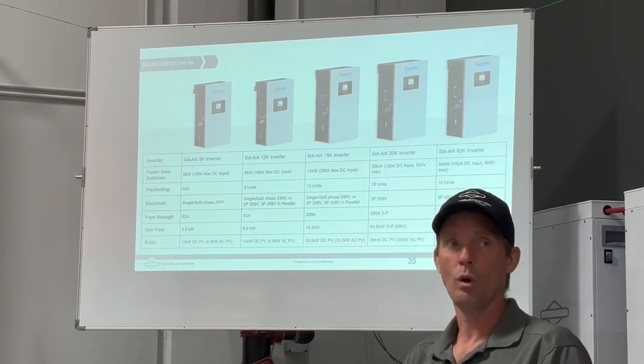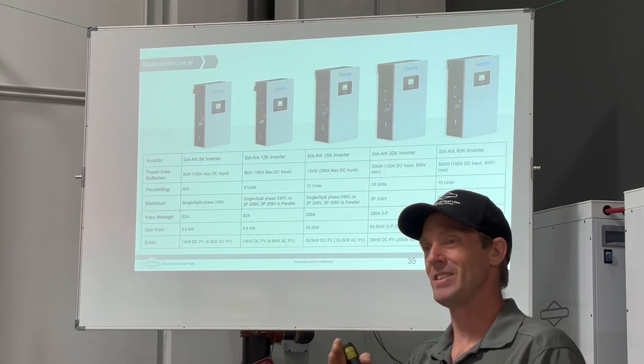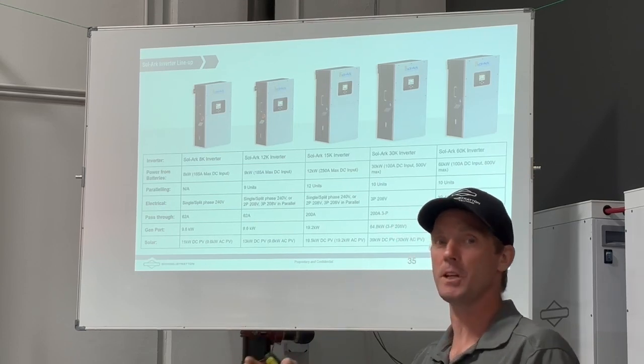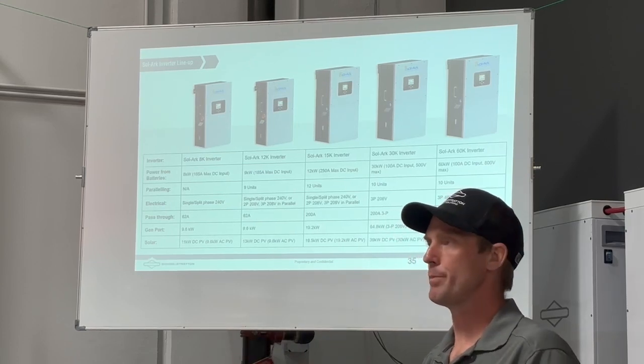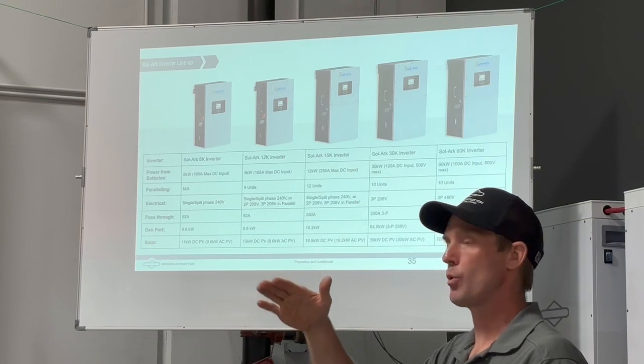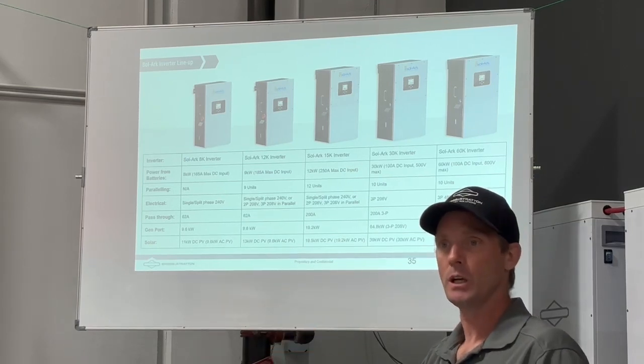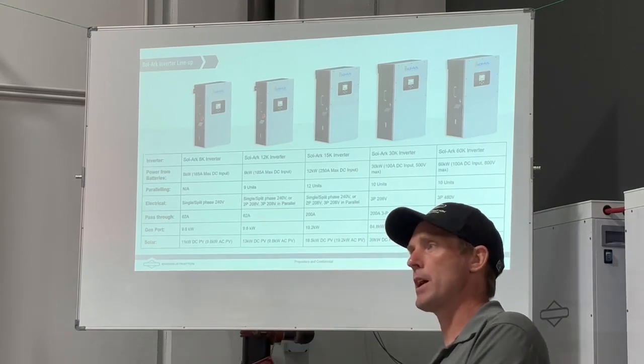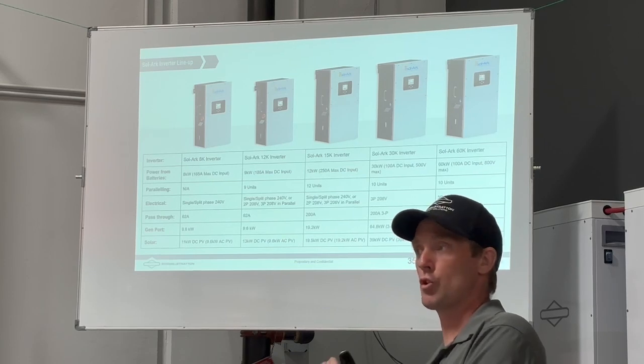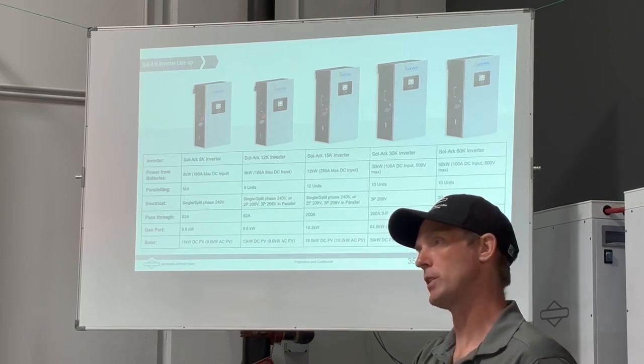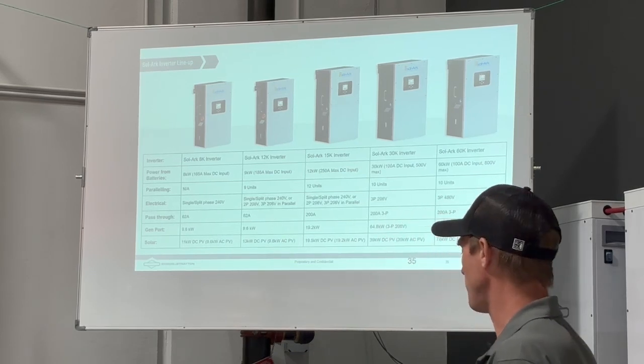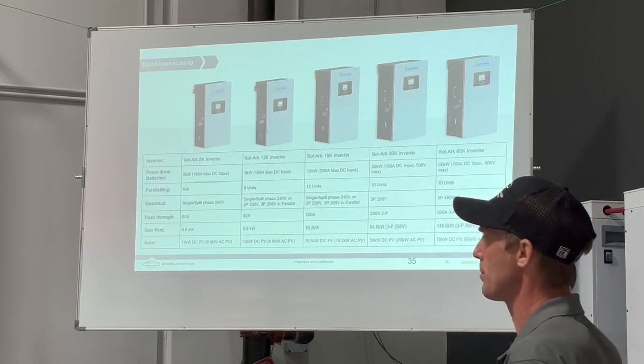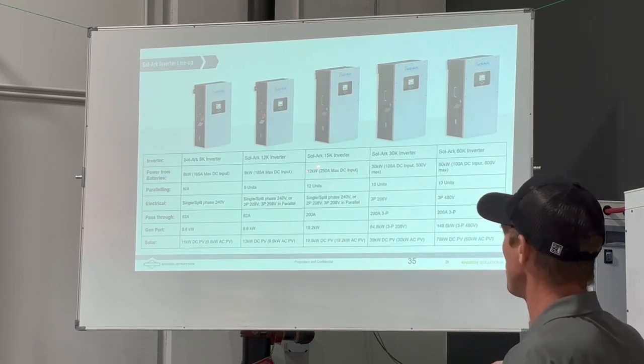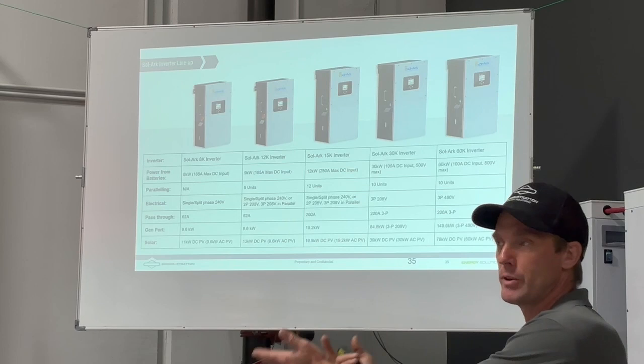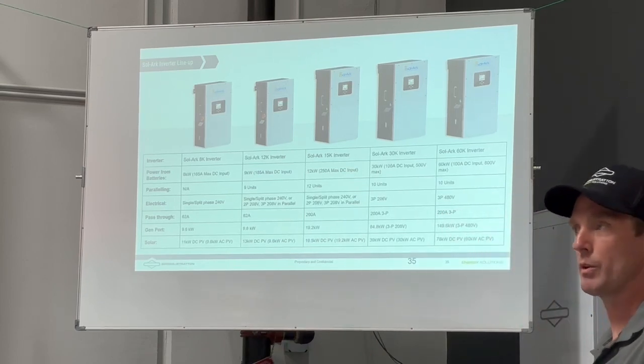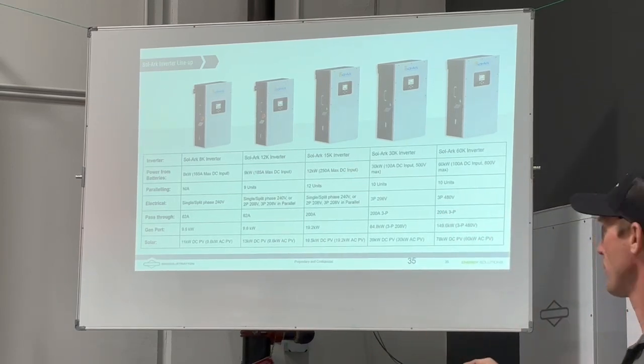I'll give you an example. The home grid battery, instead of having 16 cells in series, has 15 cells in series. So the home grid battery actually operates at about 3.2 volts lower than our battery, which means you need more current out of that battery for the same amount of power. Power is current times voltage. So if I reduce the voltage, I have to get more current. So the limitation on the 15K is actually 275 amps, but with a 48 volt battery, it'll pull 250 amps. Our battery is capable of 272, so like I said, it's more than enough to supply the power for Sol-Ark.